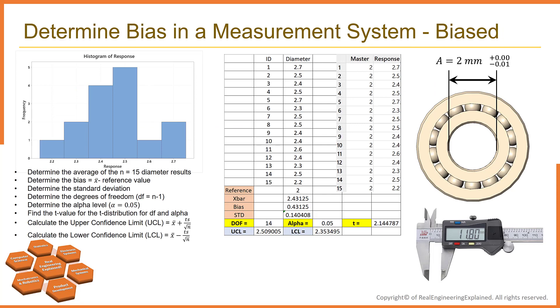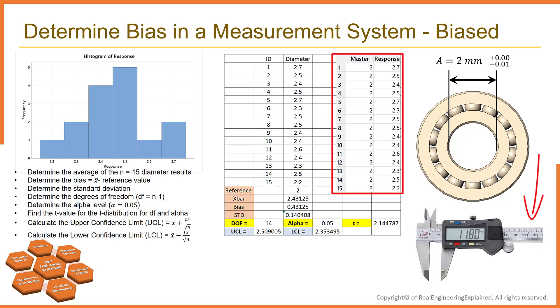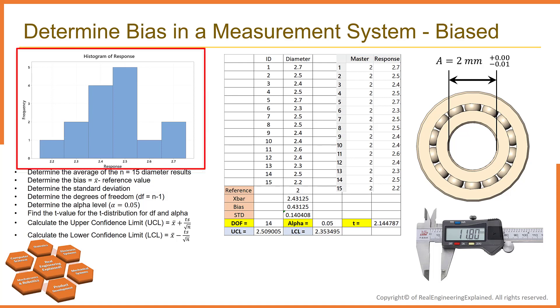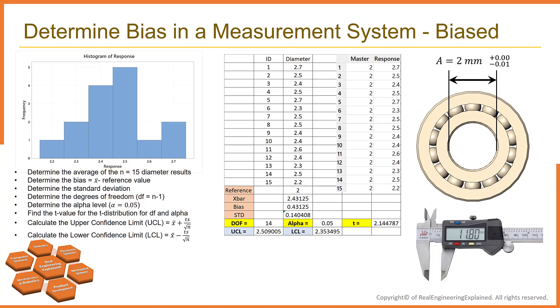Now the engineer runs a sample bearing with a 2 millimeter internal diameter 15 times with another caliper and records the results in Excel. The histogram shows that the diameter results are spread out in a pattern that indicates bias is present in the measurement system. To further confirm this, the engineer constructs a 95 percent confidence interval. If the confidence interval does not include the reference value of 2 millimeters, the engineer can assume there is evidence of bias being present.